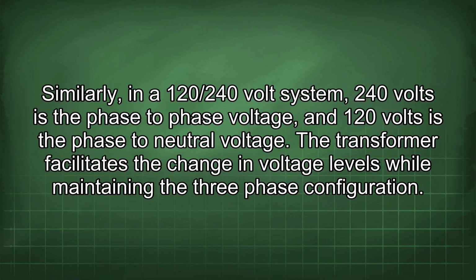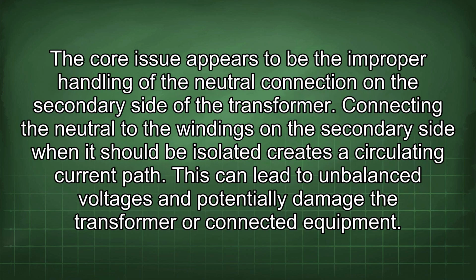Similarly, in a 120/240 volt system, 240 volts is the phase-to-phase voltage, and 120 volts is the phase-to-neutral voltage. The transformer facilitates the change in voltage levels while maintaining the three-phase configuration. The core issue appears to be the improper handling of the neutral connection on the secondary side of the transformer. Connecting the neutral to the windings on the secondary side when it should be isolated creates a circulating current path. This can lead to unbalanced voltages and potentially damage the transformer or connected equipment.